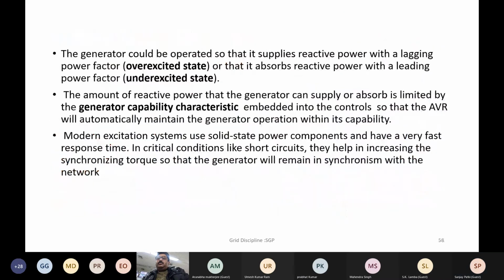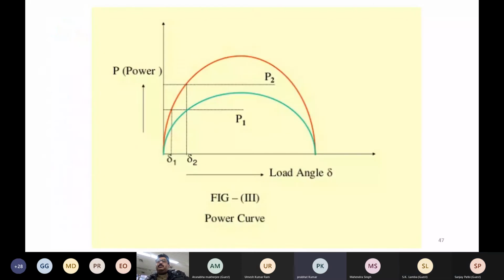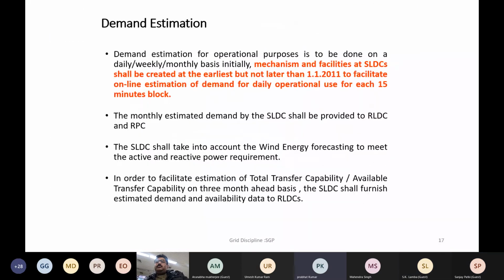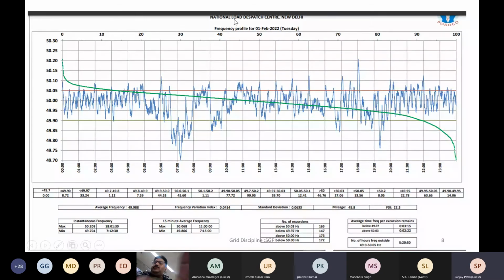It's the instantaneous frequency. Okay, but nowadays we are noticing that grid frequency is going to 49.72 sometimes. Yes. So this is the chart. That's why I showed you that this is the frequency band, and you can see this is the instantaneous frequency which is being controlled within this band. And there are occasions when frequency has gone down. For example, at this instant, the frequency had gone down to 49.7 also. So these are instantaneous values.